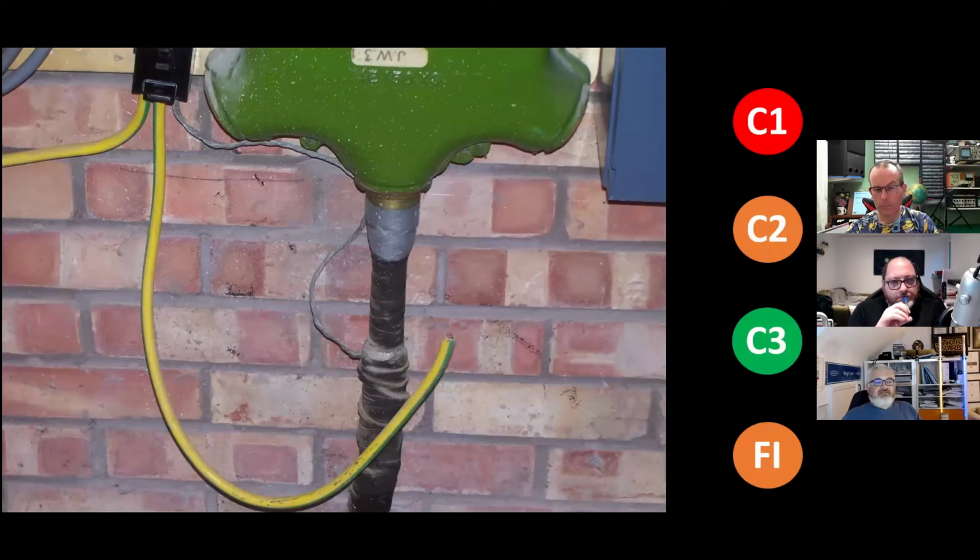And they've obviously left a conductor from that earth block, the Henley block. But instead, somebody's obviously come out and over time effected a repair and just left a braided aluminium strap. What do we think? Do you think that's suitable, sufficient? Do you think we need to remove that earth?